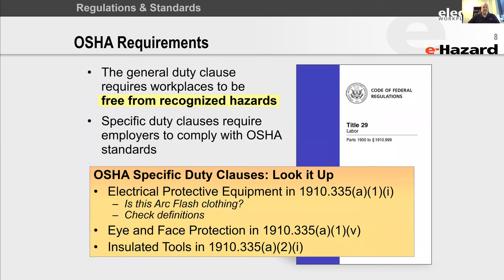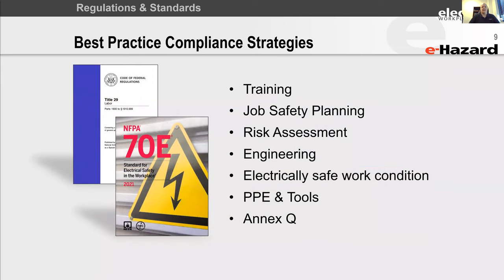Now, OSHA states that we have to create a workplace that is free from known and recognized hazards. They really tell us that the first thing we're going to do is shut the power off, right? But OSHA is more high level, performance based. This is what we have to do, not necessarily how we do it. That's where standards like 70E and 462 come into play, because they start to develop what we need to put in place to meet those requirements of the OSHA standards.